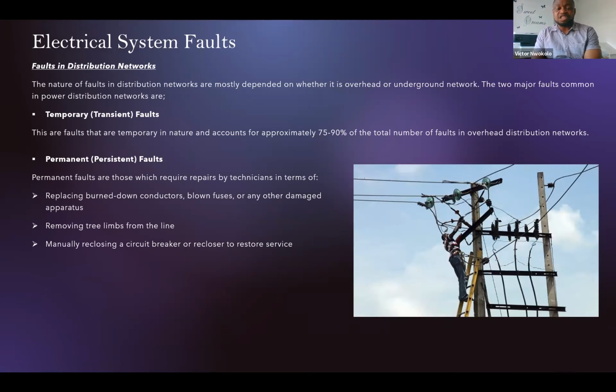So, fault in distribution system. In a distribution system, we basically have faults classified as temporary or permanent. When a temporary fault occurs, equipment used to supply protection operates to isolate the fault. A transient fault in a distribution system will then clear the fault. Where that fault fails to clear within a short time, it can easily transit into a permanent fault. An example of that is if a fault is not cleared off a line, a fuse is blown, and we now have to carry out a repair on that line, it becomes a permanent fault.